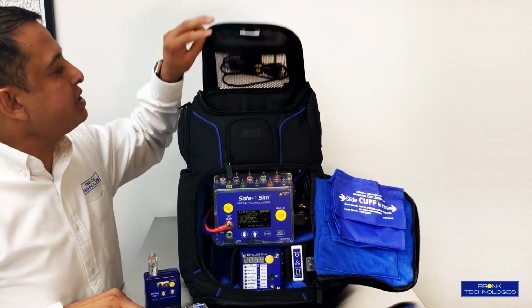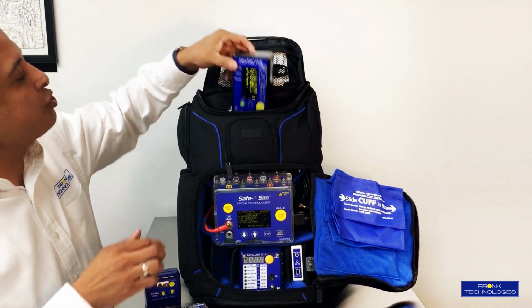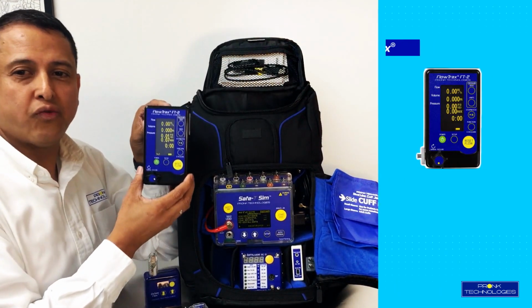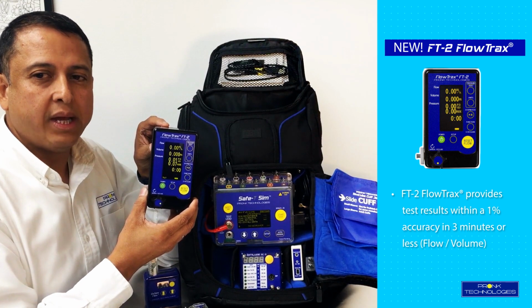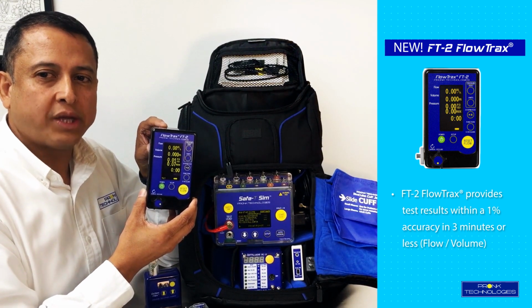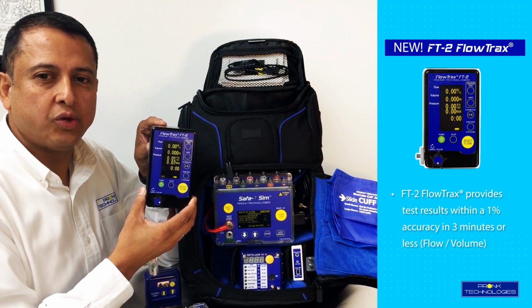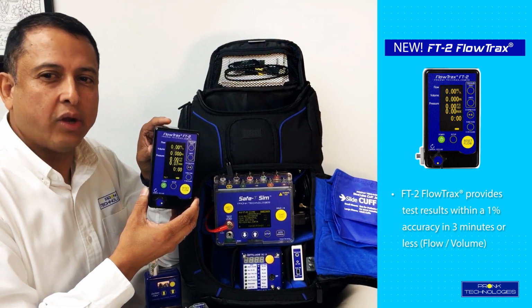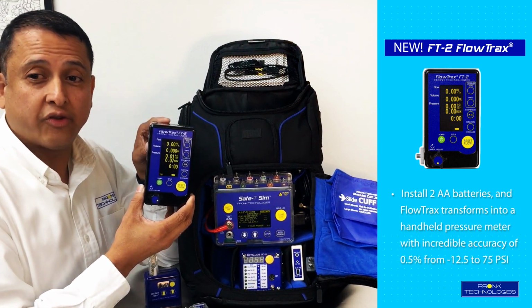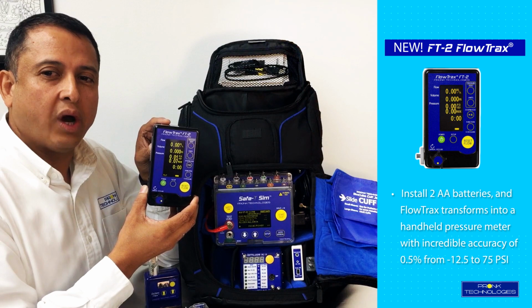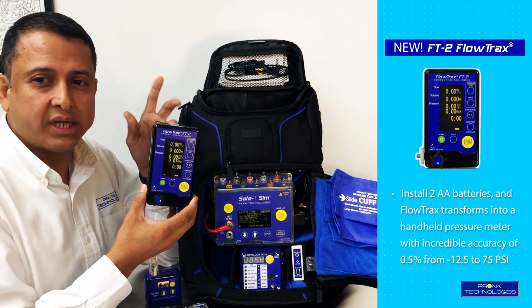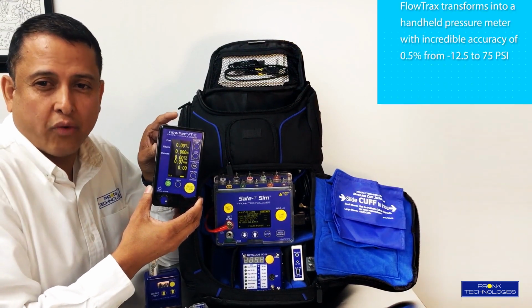The next product is the FlowTrax Multifunction Infusion Pump Analyzer. It's a great tool for testing any type of infusion pump. The integrated pressure meter also makes occlusion testing quick without the need to change your setup. The unit functions as a standalone pressure vacuum meter as well, with a range of -12 to +75, so you can test any type of medical device for pressure or vacuum.